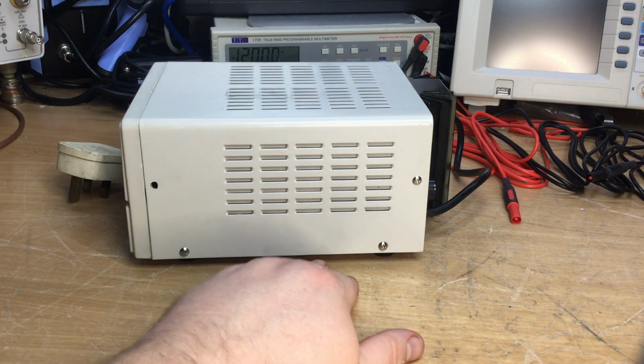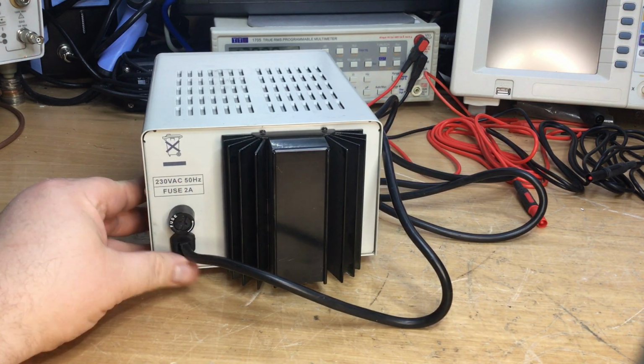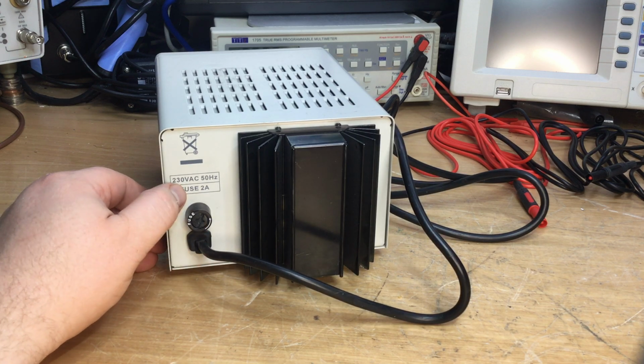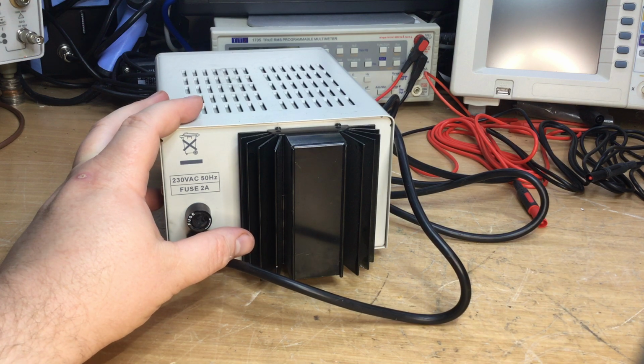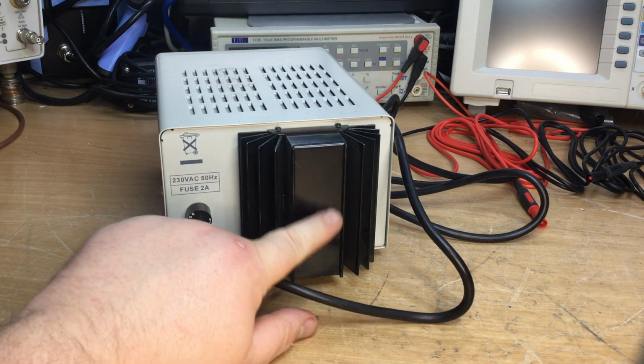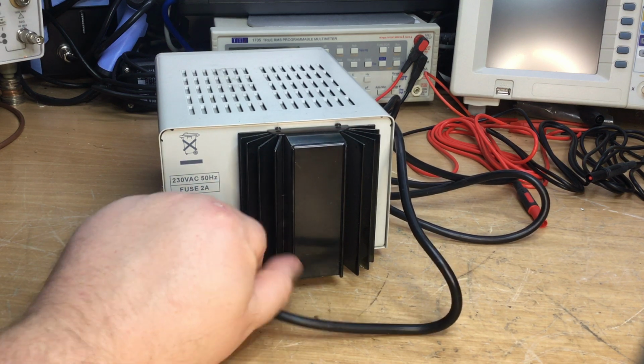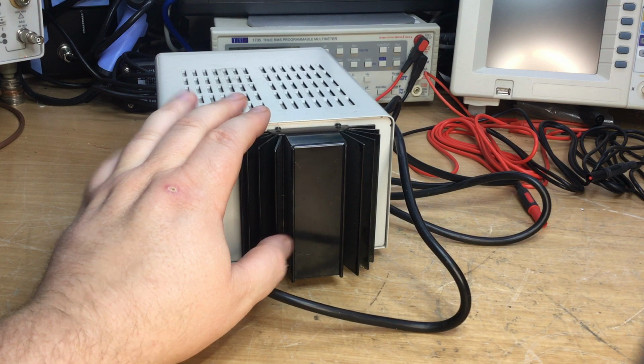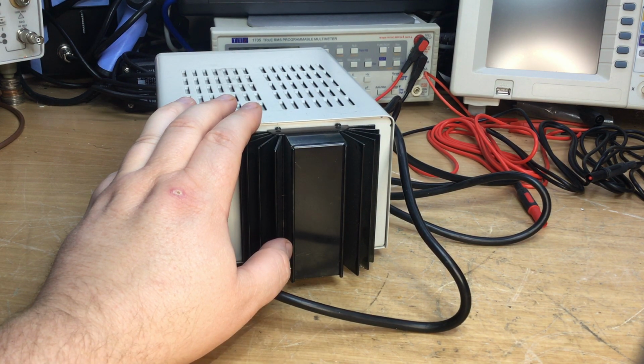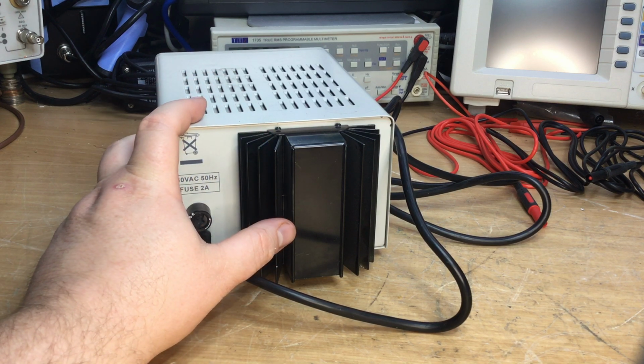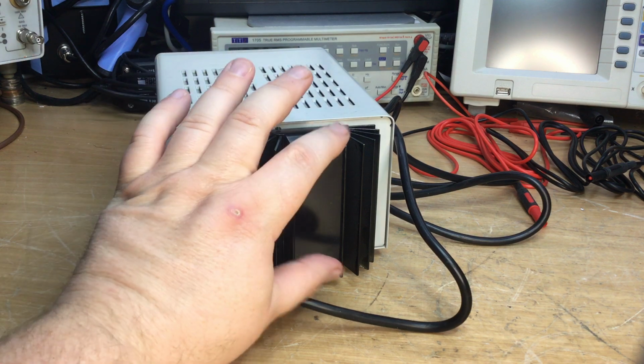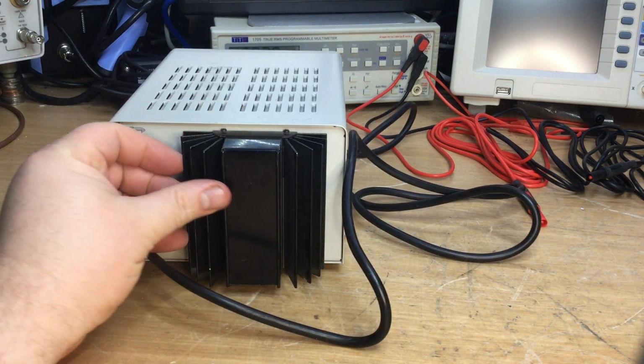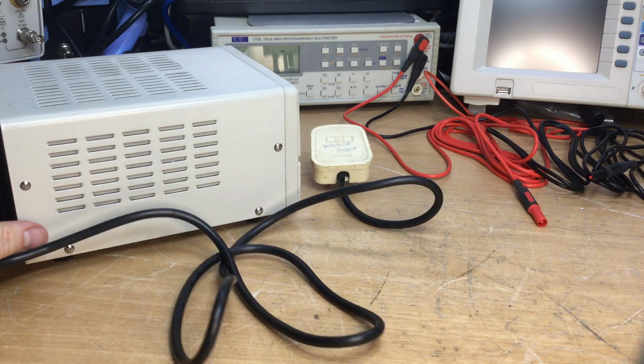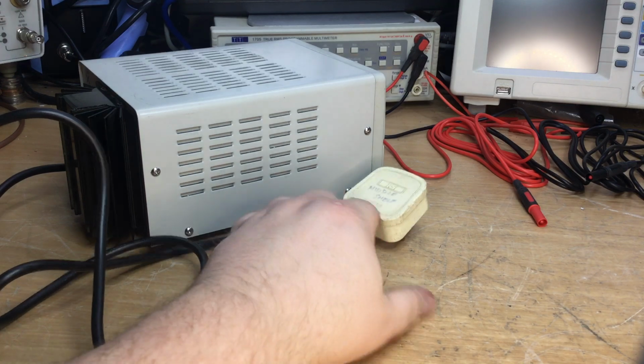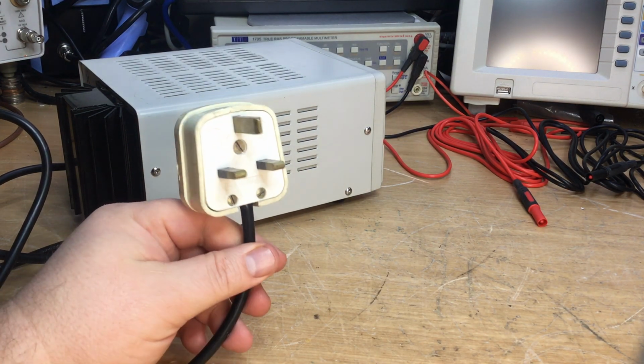So we've got 3 screws in there, and on the rear we've got the usual fuse and mains cable coming in, 230 volts AC at 50 hertz like we use here in the UK, with a 2 amp fuse. Underneath here we'll have the series pass transistors, which is what we've had fail on other power supplies - if you look at my earlier videos, there are repair videos of really high current power supplies delivering 30, 40, 50 amps and upwards where these transistors failed. It's quite a small heat sink and doesn't seem to be fan cooled from what I can see. On this side all the screws are there, the plug's not in bad nick, and there's no damage to the cable from what I can see.